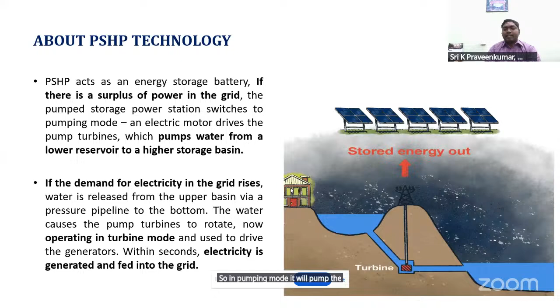When coming to the efficiency of the pumped storage power plant, the overall cycle efficiency is about 75 to 80%. Nowadays it is reaching up to 82% also. If you give 1 megawatt hour, we will get an output of 75.